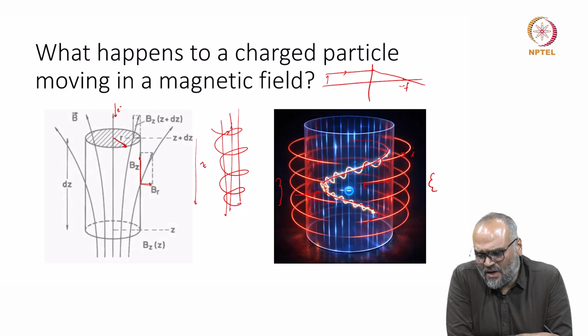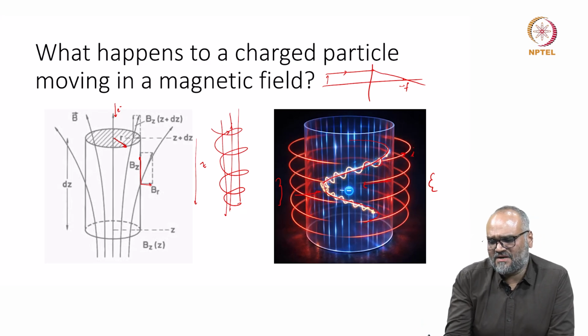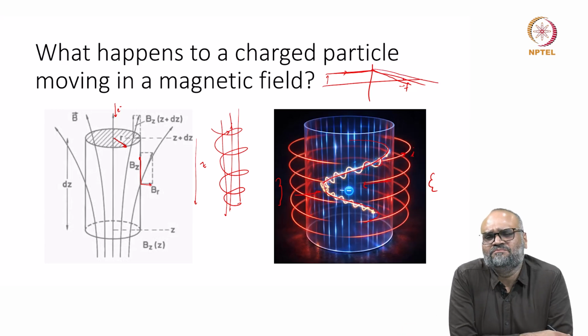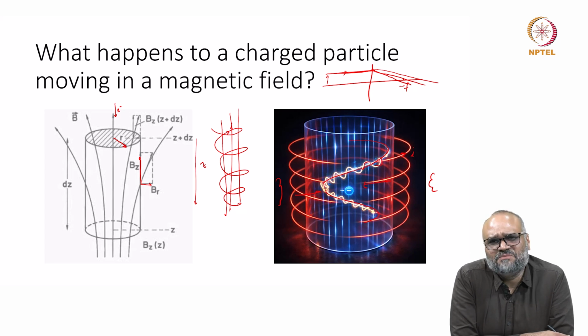So, what you are changing by changing the magnetic field strength or by increasing or lowering the current is the point of convergence of the electron beam after the rays go paraxial to the optic axis. You are allowing them to converge either before the previous focal point or further away from the focal point. So essentially, you are also changing the focus of the magnetic lens by simply changing the field of the electromagnetic lens.